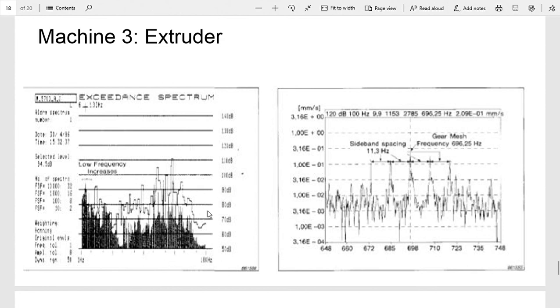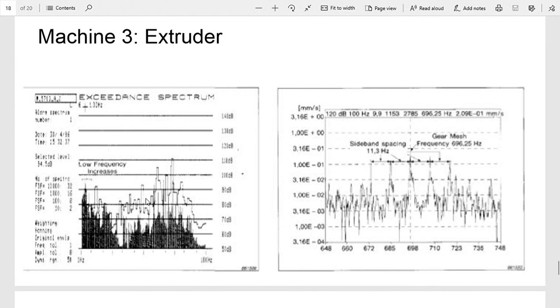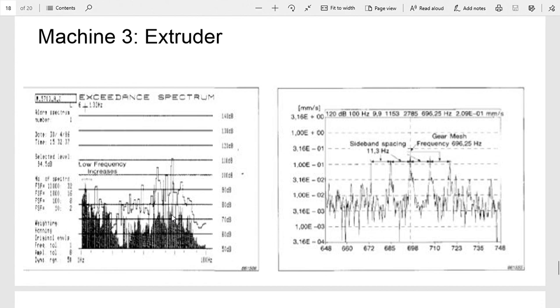One of the damages they found in these was low frequency increases. In this graph you can see the dark, and then there's a second graph kind of laid over the top. You can see pretty much increases along this whole band of frequency. This was from small needle bearings that carry shafts in the extruder itself.